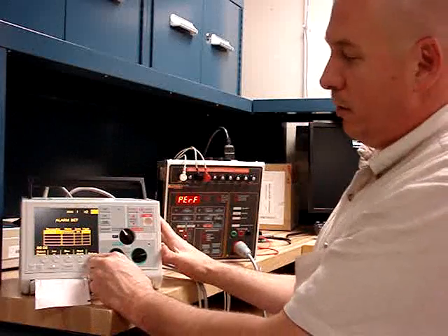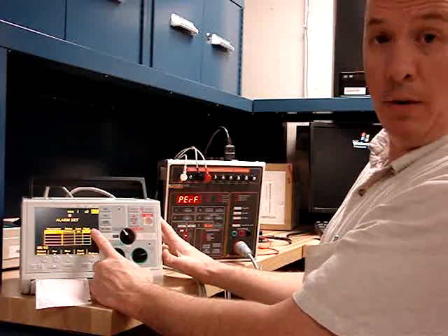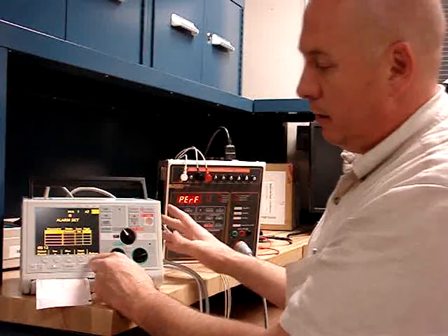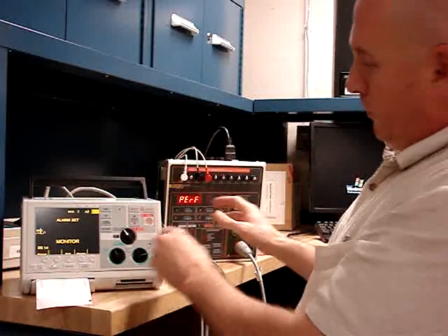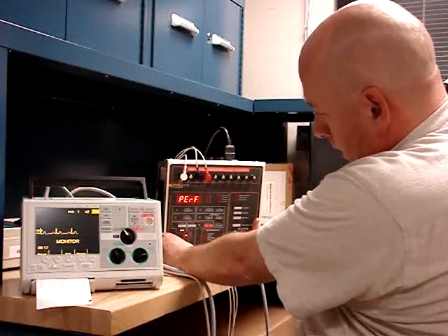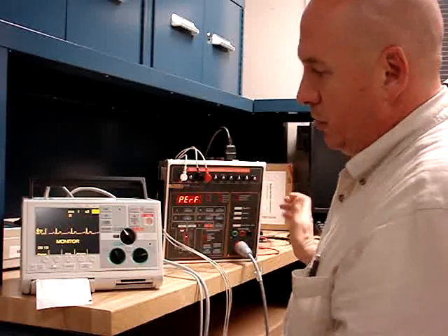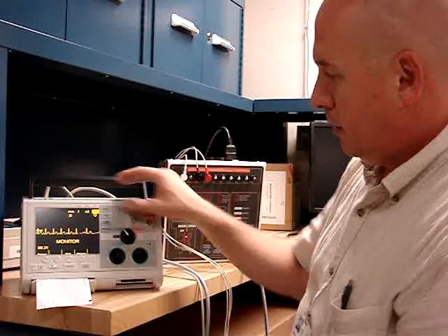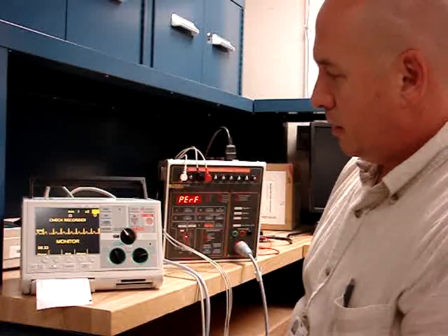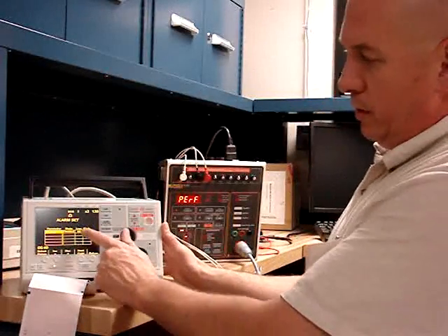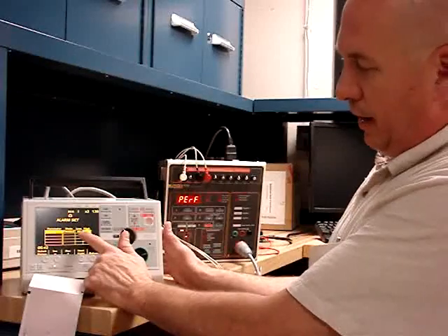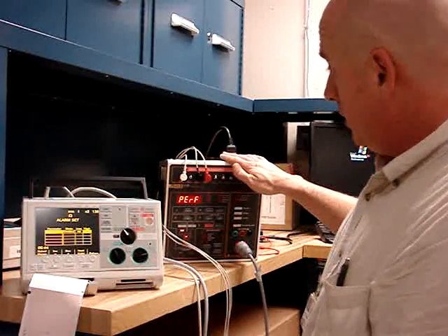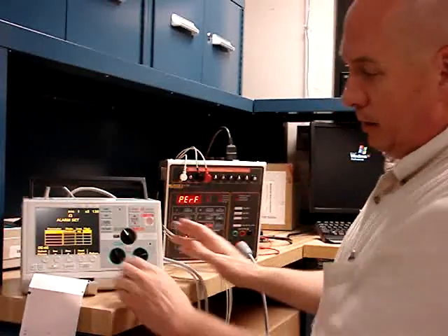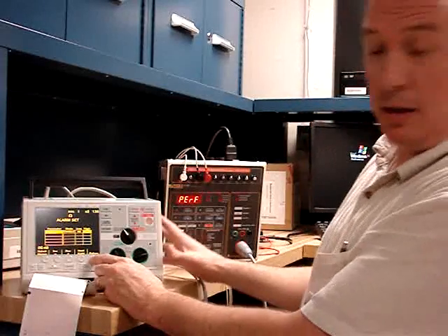Checking the alarm, we are going to set the alarm high rate at 115. So we check that. So now we're going to set this at 120, and it should go off when it hits. There's one. For checking the low rate alarm, we are going to set this to 65, and we will change the simulator to 60. So when it hits 60, it should alarm.